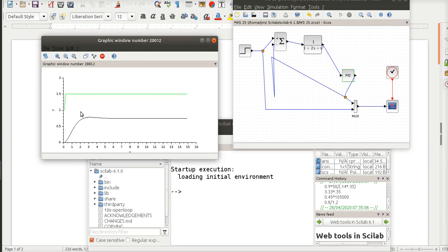That is our R. We need to come up with our L, which would be this slope projected down to the x-axis, and the time between the step change and where that slope crosses the x-axis is your delay time. So in this case, our delay time is probably around 0.35 seconds, somewhere in that neighborhood. It's not very much.